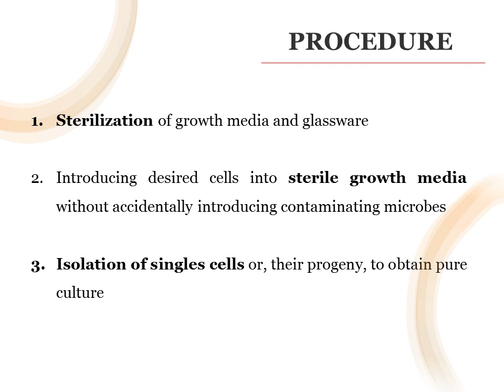First is the use of autoclave, which is done for contamination free glasswares, plasticwares as well as media, where heat at a temperature of 121 degrees Celsius and pressure at 15 pounds per square inch is used. So it basically employs wet heat as the source of sterilization. There are some fluids which are heat sensitive, some antibiotic solutions or maybe some media which cannot withstand all the heat and pressure present in the autoclave. So for them, a physical sterilization method is used where specially designed filter paper discs are put onto a holder which, after being closed, creates a vacuum, and then the fluid is passed through this mesh and the filtrate that is collected is contaminant free.